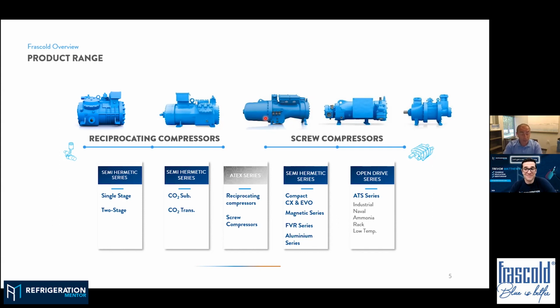Since you mentioned CO2, don't forget that we can still have CO2 and propane in conjunction. We have seen a lot of applications in medium and low temp where the CO2 is pumped into the machine room, and on the compression side we have propane or ammonia, for example. So we still have all the advantages of the smaller pipes and the heat transfer, but only pump CO2 into the cold rooms. Yeah, that's awesome.